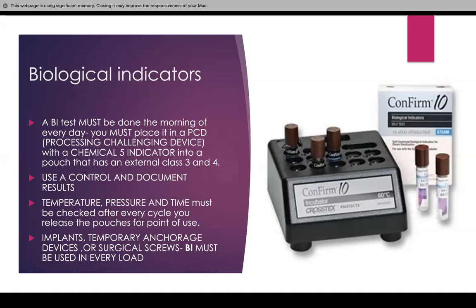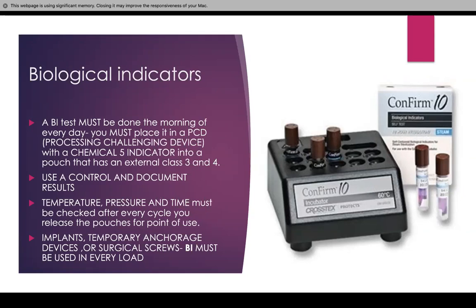What is a control? In that little machine, there is going to be one labeled C that we place at the same time as the one that has been processed in the sterilizer. Temperature, pressure, and time must be checked after every cycle before you release the pouches for point of use. We do this in the morning, and what allows us to release it is checking that the parameters — time, pressure, and temperature — have been met.